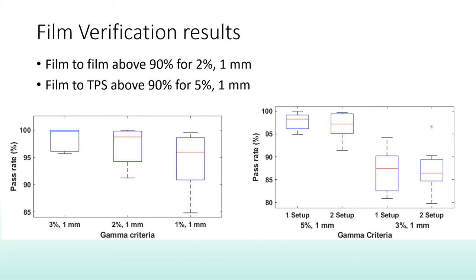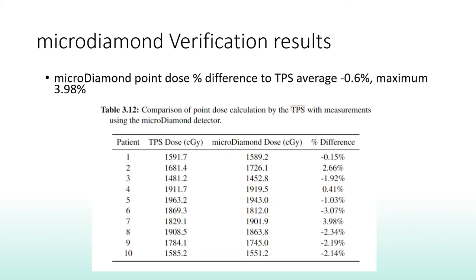Film results showed that setting up the phantom twice did not introduce additional errors. Point dose verification resulted in an average percent difference to TPS point dose at the isocenter of minus 0.6%, with a maximum percent difference of 3.98%.